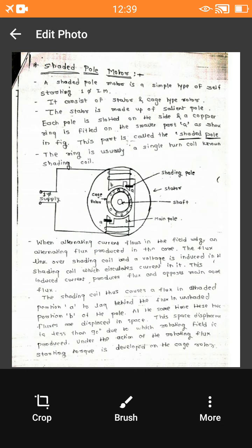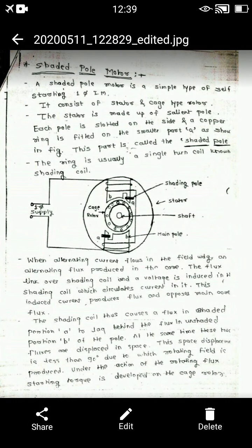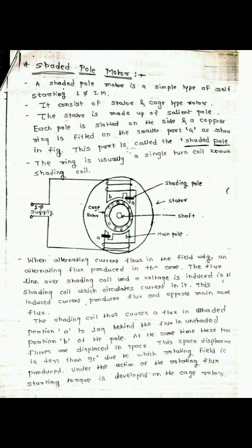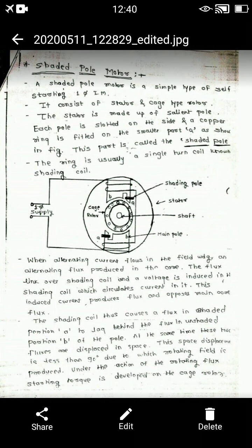This is called a shaded pole induction motor. The shaded pole induction motor is a simple type of self-starting single-phase induction motor. It consists of a stator and rotor. The stator is made up of salient poles. Each pole is slotted on the side and a copper ring is fitted on the smaller part, which is called the shaded pole, shown by letter A. This ring is a single-turn coil known as a shading coil.